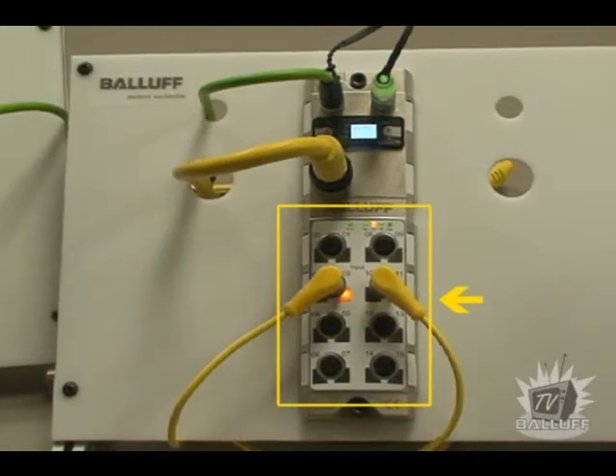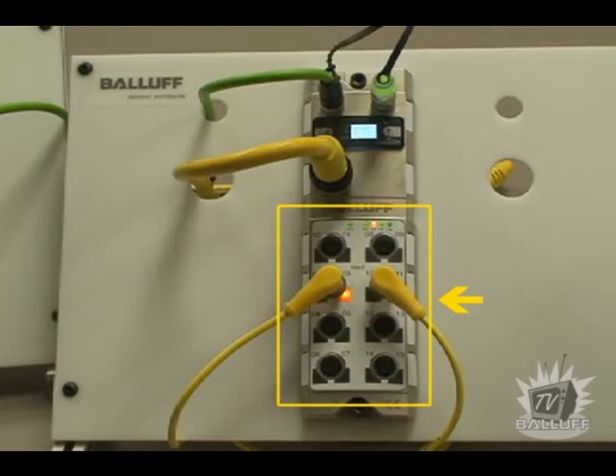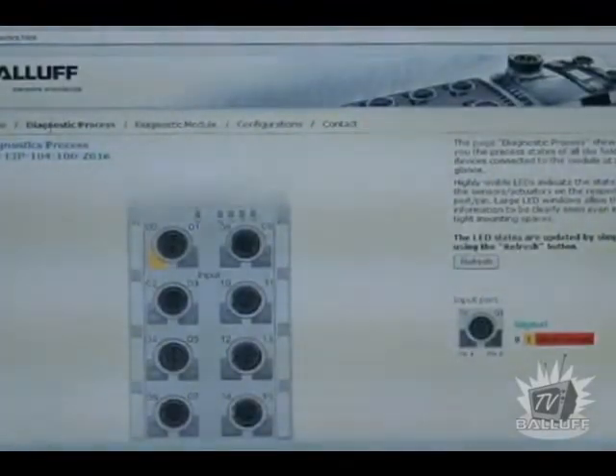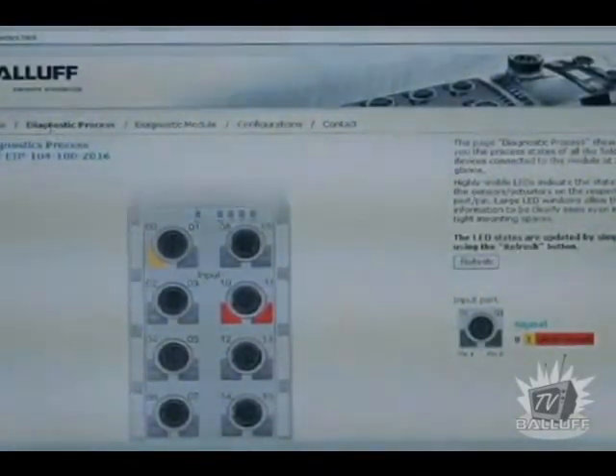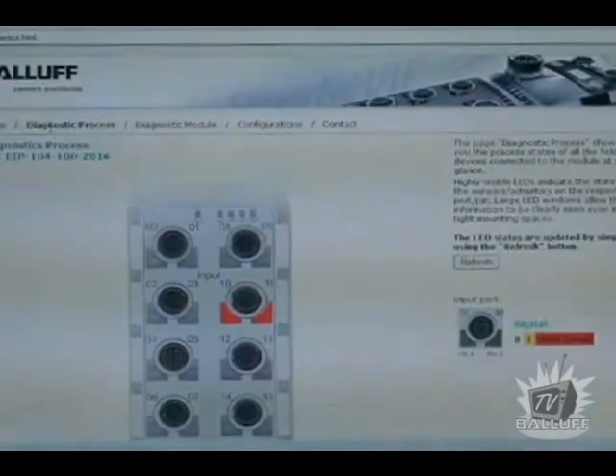Finally, each portion of the block provides a signal indication with large LEDs and diagnostic short-circuit or overload status. All of this information is also available in the process data at the controller and can be viewed using the built-in webpages for the blocks.